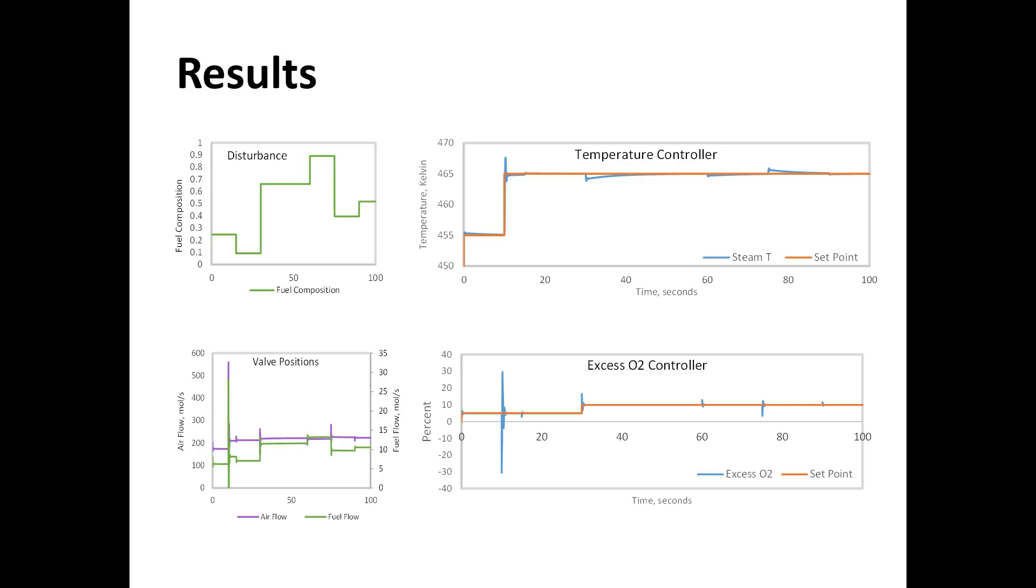We believe our controllers were successful because the temperature of the steam never varied by more than one or two degrees and the excess O2 may have jumped a little bit but it went back within about a second. Not much bad is going to happen within a second.